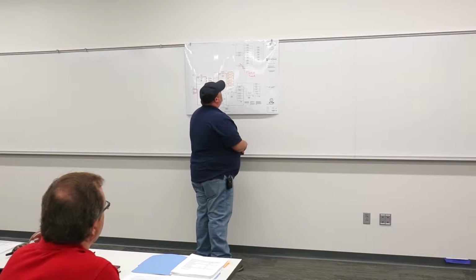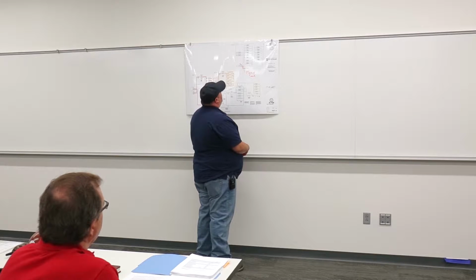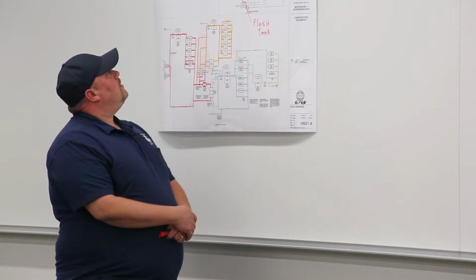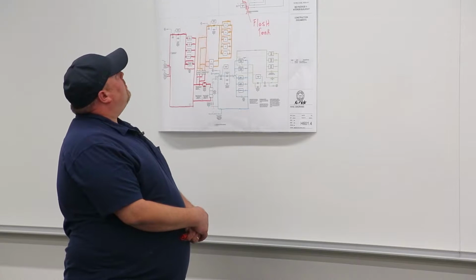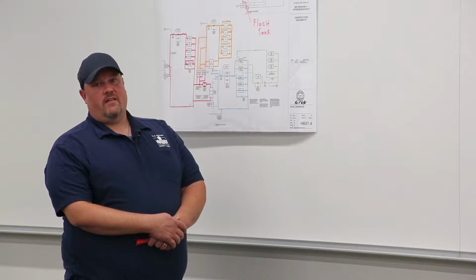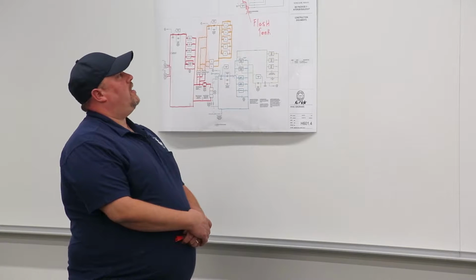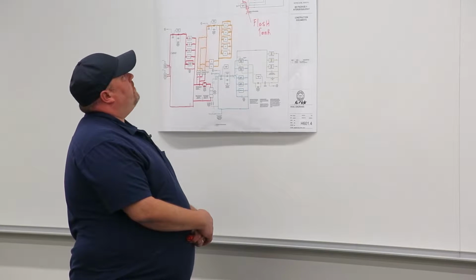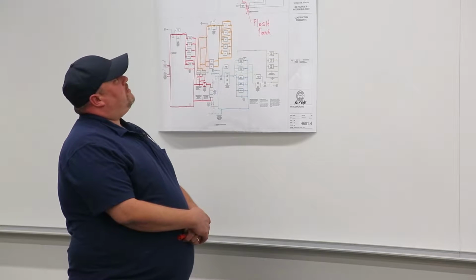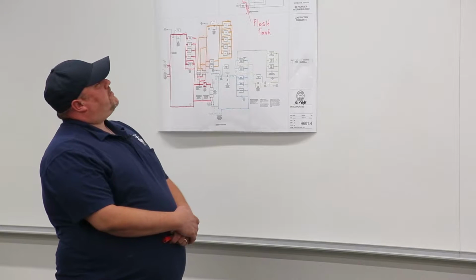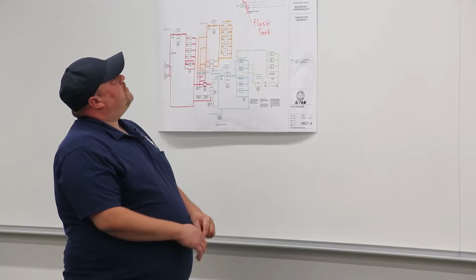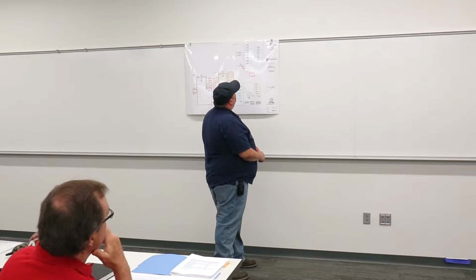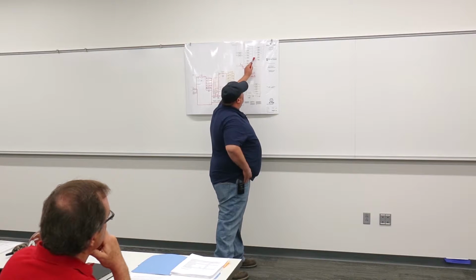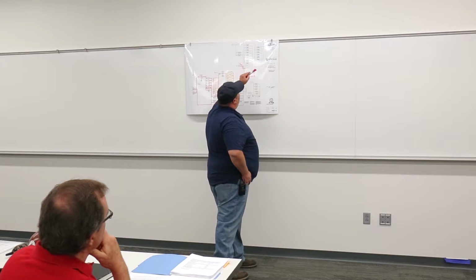As it comes in the building from the plant, we've got two different steams. We've got a medium pressure and a low pressure steam system. Medium pressure runs at 70 psi and low pressure runs at 10 psi. The medium pressure steam comes into our building basically just to feed the autoclaves that are located throughout the building. And we have several taps for future autoclaves. Right now we have 3.